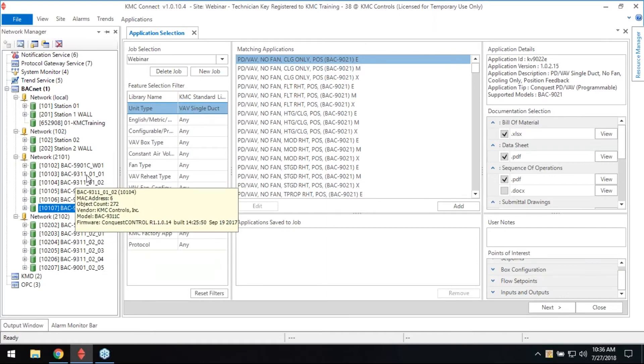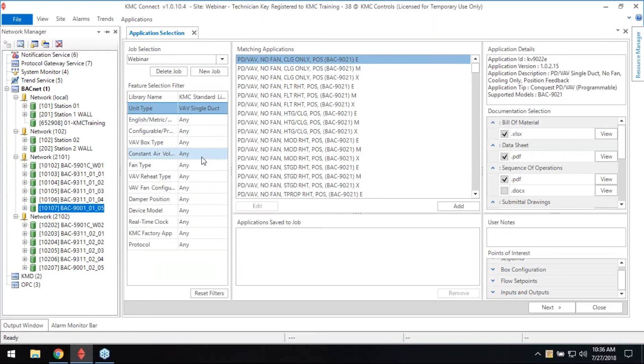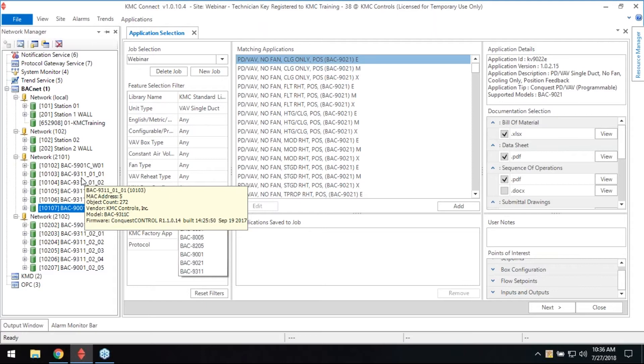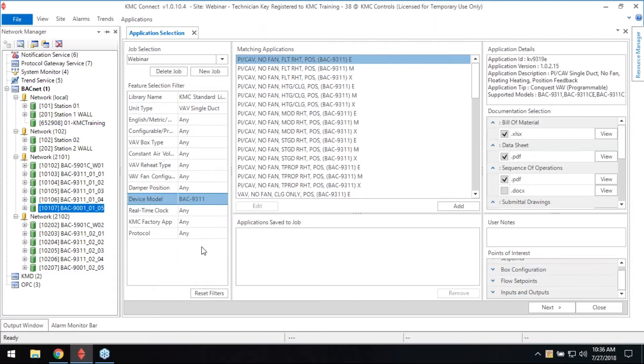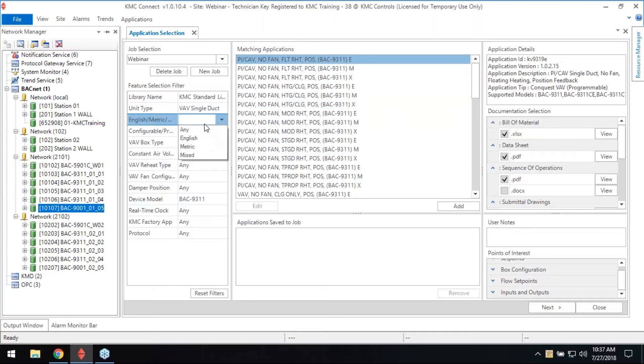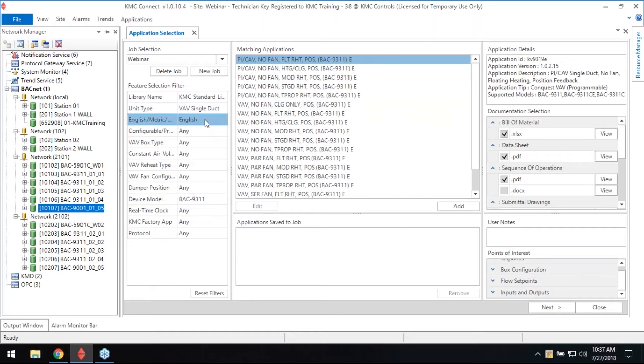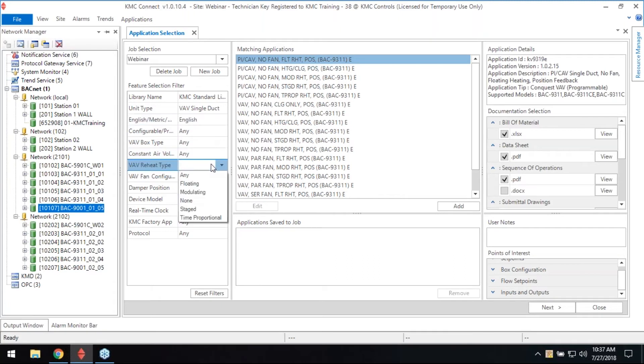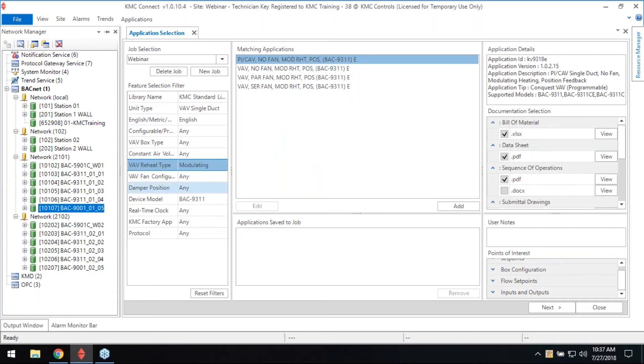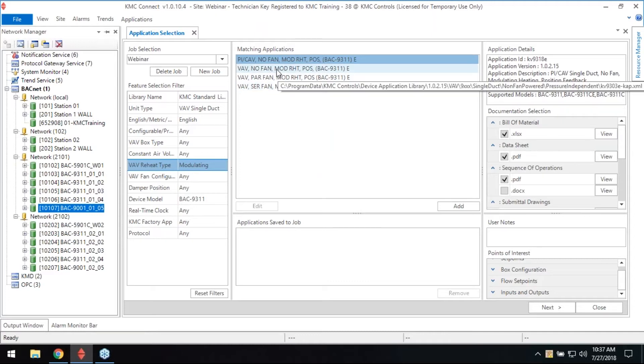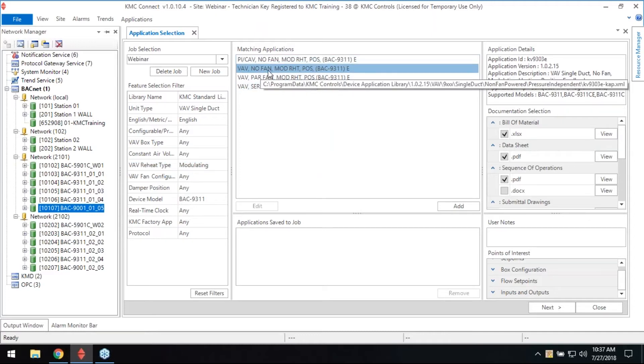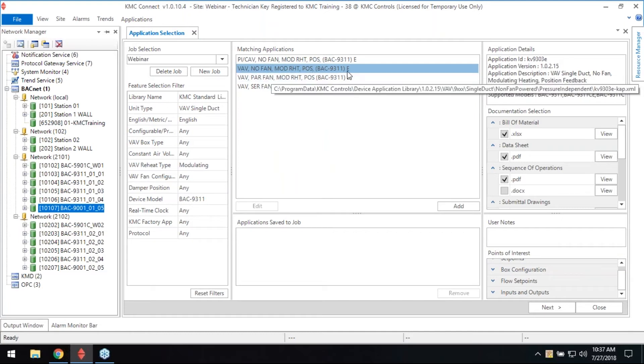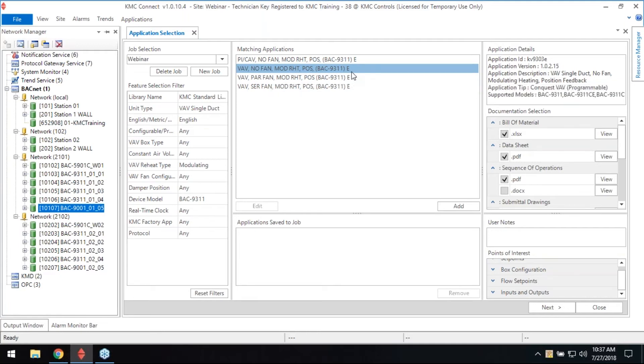So I'm going to go through and pick these 9311 VAVs. I can just come right down here to speed this process up. I know I have a 9311 because that model number is right there. That filters out what's going on over here. I'm just going to say it's English instead of metric or mixed. So reheat type maybe modulating. I'm going to select this one because I know it's no fan modulating reheat position feedback.